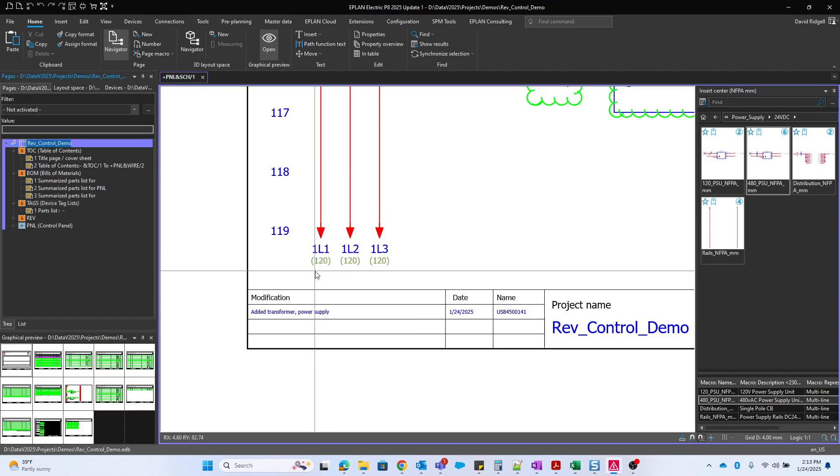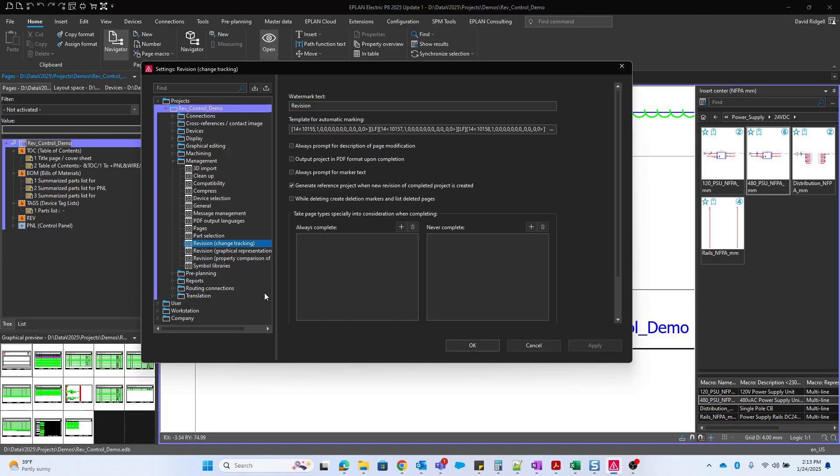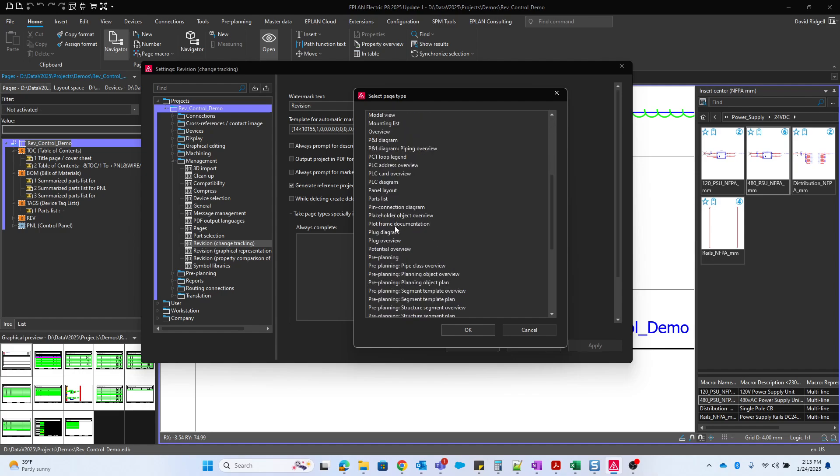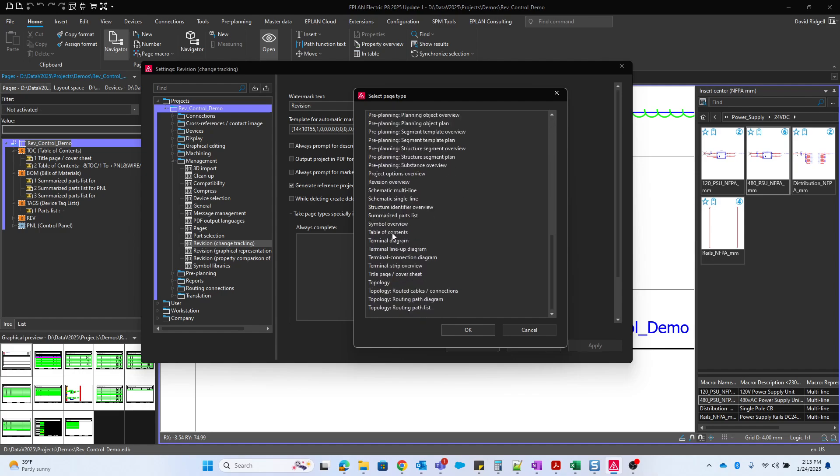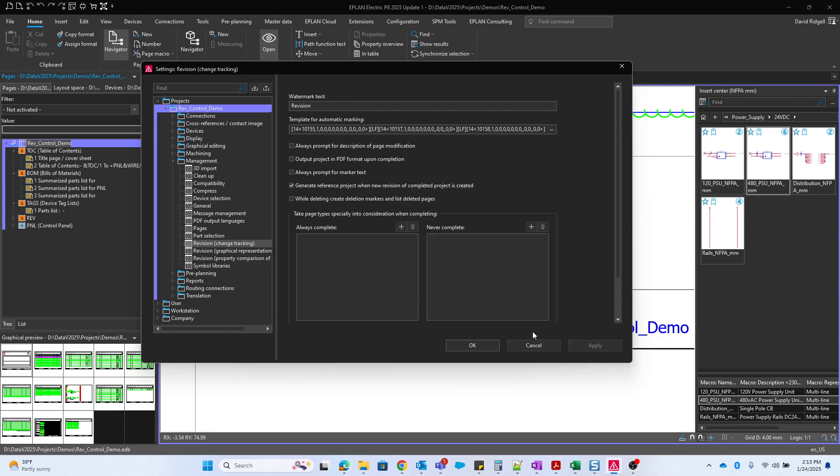If you wanted that to be project-wide and you want every page to get indexed, you have to add here under always complete, you would have to add the different page types that you want to get completed. So obviously schematic multi-line is probably the most common, single line, overview, and so on. But typically it's only pages that were actually changed.